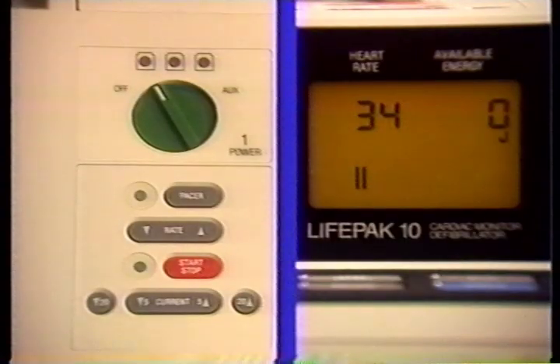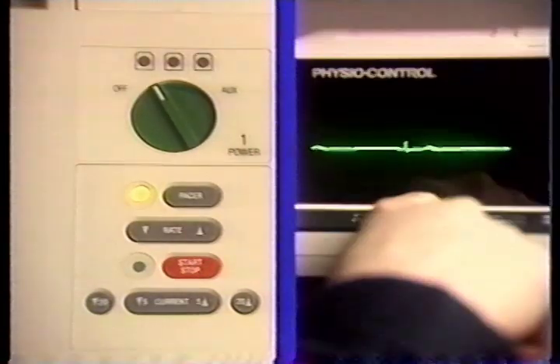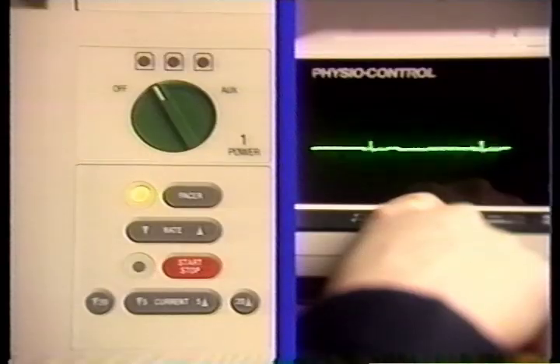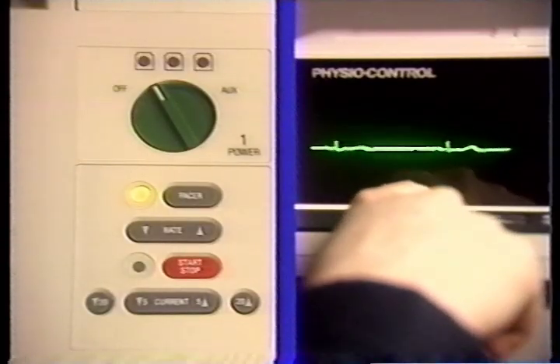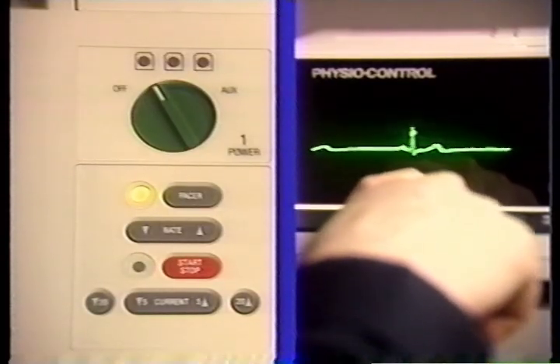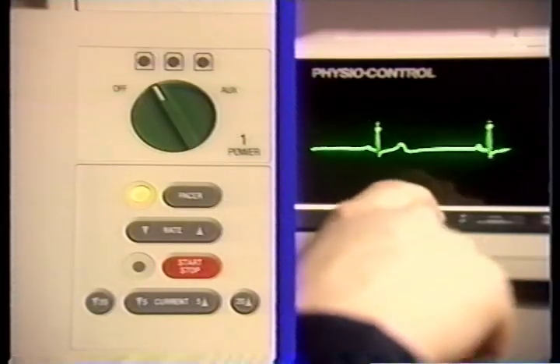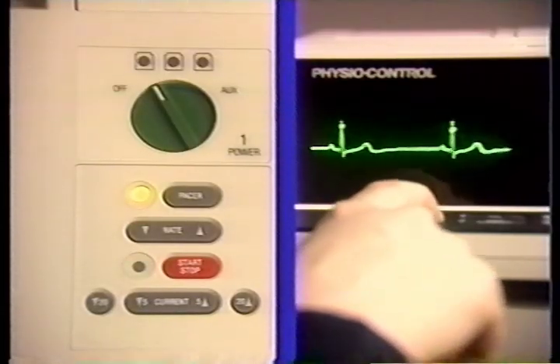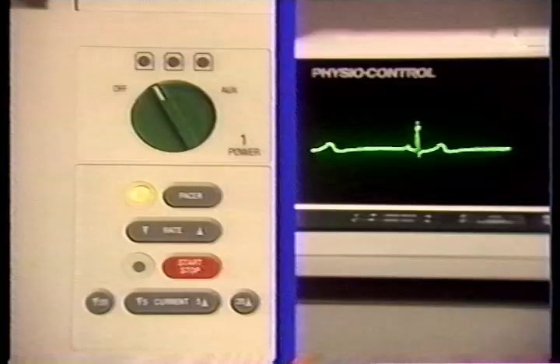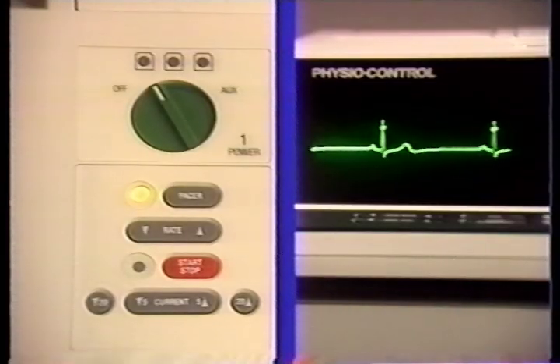Push the pacer button to activate the pacemaker. The status display will now show the pacing rate instead of the heart rate, and current in milliamps instead of joules available. At power up, the pacing rate is preset at 40 beats per minute and the current at 0 milliamps. If intrinsic beats are present, adjust ECG size until the sense marker is seen on each QRS. Adjust the QRS volume until a beep is heard with each QRS complex. If the patient is asystolic, omit this step.